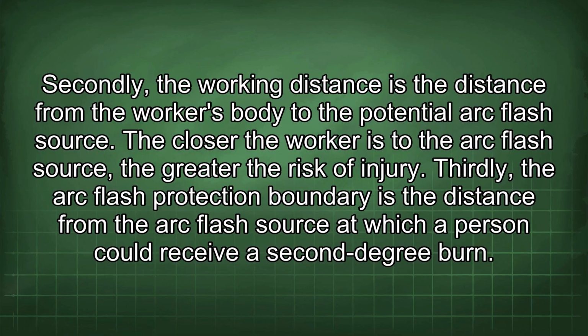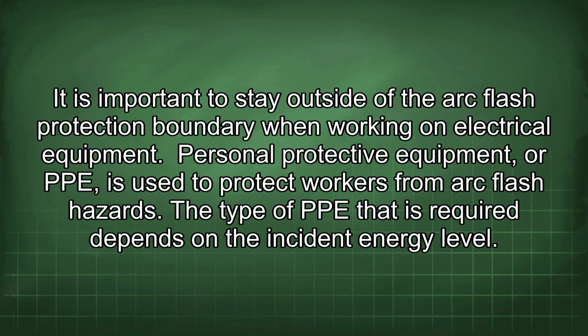Thirdly, the arc flash protection boundary is the distance from the arc flash source at which a person could receive a second-degree burn. It is important to stay outside of the arc flash protection boundary when working on electrical equipment.